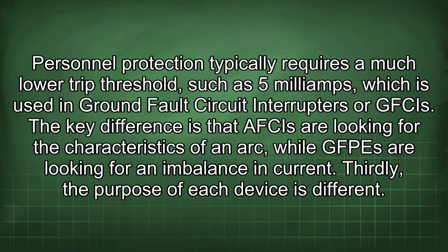Personnel protection typically requires a much lower trip threshold, such as 5 mA, which is used in ground fault circuit interrupters or GFCIs. The key difference is that AFCIs are looking for the characteristics of an arc, while GFPEs are looking for an imbalance in current.